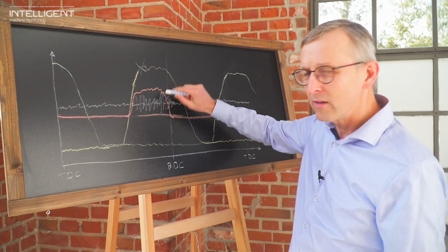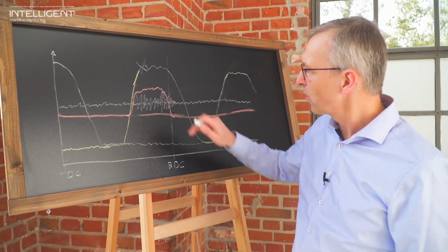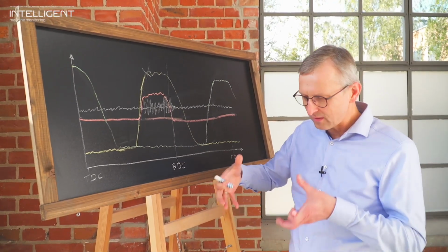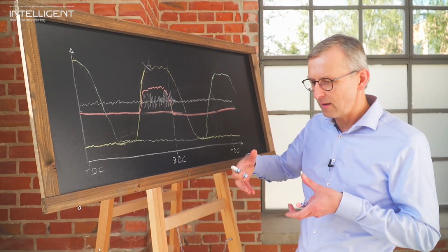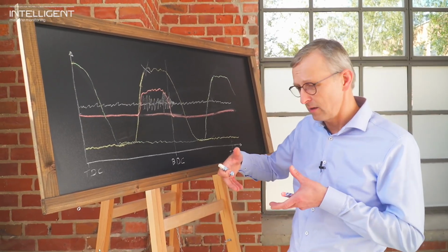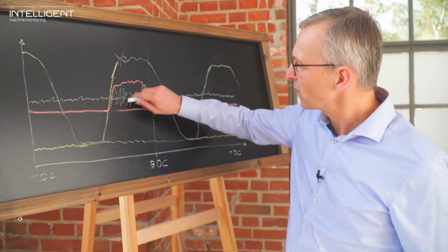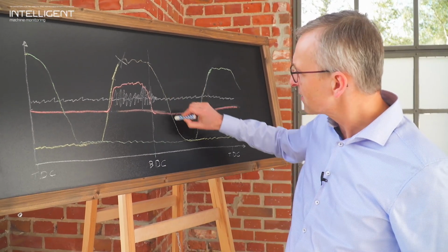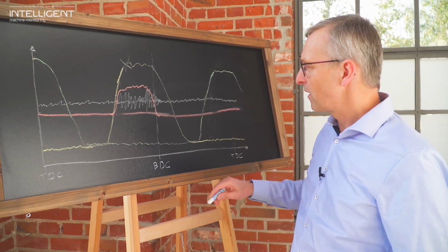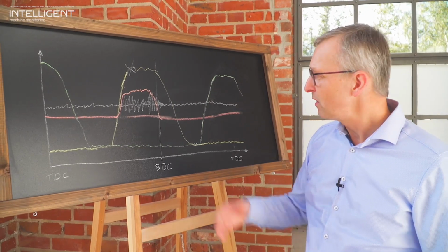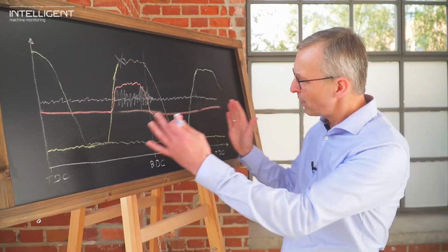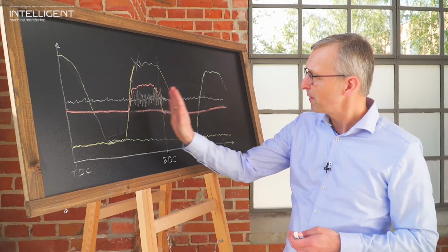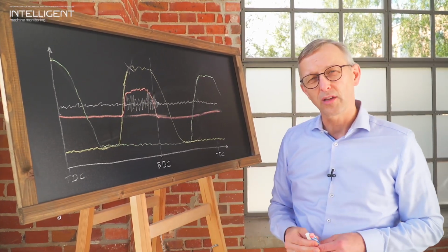At the same time, we have high vibrations, which are because some of the fluid is passing our discharge valve, and also our piston is not nicely guided anymore by our crosshead, because it's floating, so there's a lot of vibration created by that. And what we can see then, when the pressure after the bottom dead center is decreasing again, everything comes back to normal. Now, to detect this effectively, you need to monitor every single revolution, and you need to have an automated way to detect different changes in different locations of your rotation.